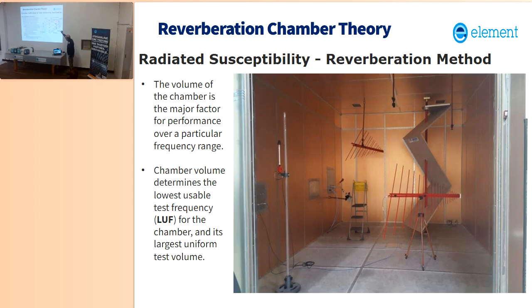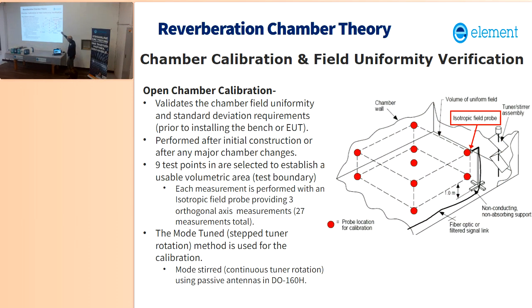And this is the calibration process. You've got 9 positions, 3 axis probes. So you're getting 27 different values at each frequency. It's a very complicated process. Brandon can tell you how long it takes. But we do this detailed field uniformity measurement to validate that we've got a uniform field within a certain standard deviation across the frequency range.